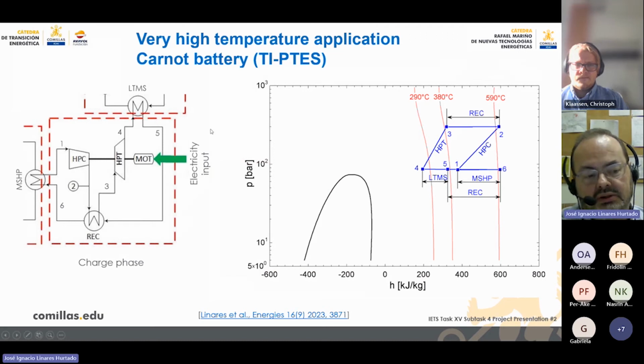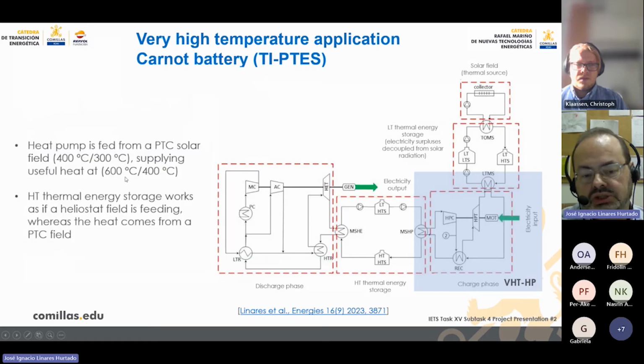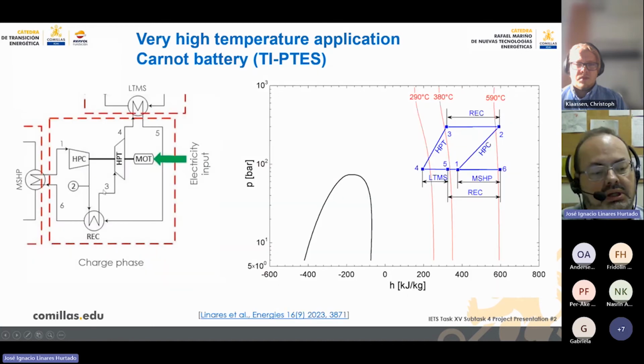This is the detail of the behavior of the heat pump, as you can see here. In this heat pump, because we are using high temperature storage here and low temperature storage here, we are using this layout when the heat exchanger to the demand is in the suction of the compressor, that is in the low pressure. Okay. This is the pH diagram taking into account this position.